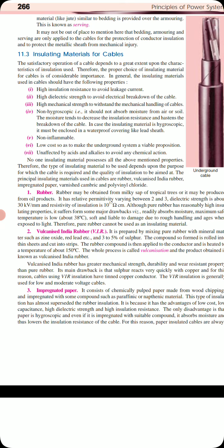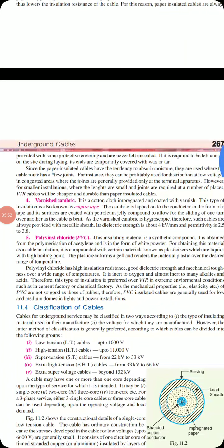Then impregnated paper, most commonly used varnished cambric, and polyvinyl chloride, PVC as we usually call it. So these are the different types of materials used as insulating material for the cable. PVC is polyvinyl chloride. It has high insulation resistance, good electric strength, and mechanical toughness over a wide range of temperatures. It is inert to oxygen and almost inert to many alkalis and acids.